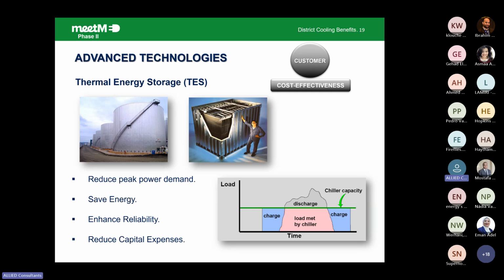So we are seeing the thermal energy storage reducing the peak power demand, and it also allows us to operate the chillers at their peak efficiency. When the chiller efficiency is at 80%, we are running the chillers at 80% of their load and get the best efficiency, and save whatever energy is in excess to the chillers, and avoid start-stop of the chillers continuously. So this is enhancing reliability.